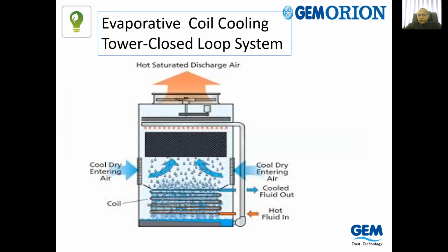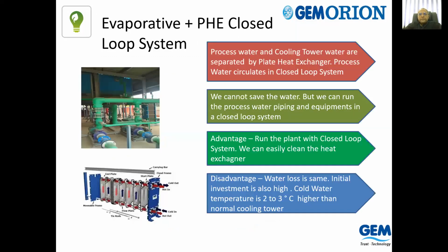Here, the process cooling, the machine cooling water will be in closed loop, but the water scaling will happen only in the cooling tower. So evaporation losses will remain, but your maintenance cycles are shifted towards the cooling tower side. Another alternate option to a conventional cooling tower is to use a heat exchanger in between the cooling tower and your system process. It's almost the same as the previous product.